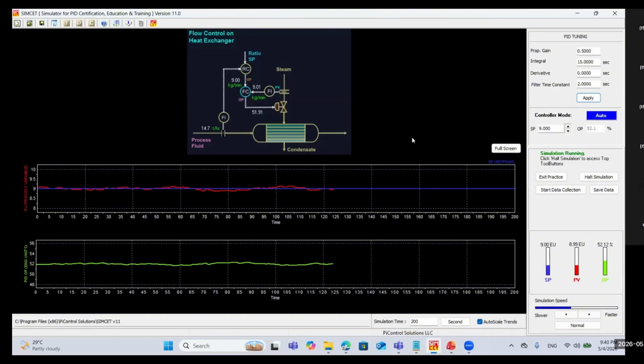Well, there are a lot of mistakes, but one of the biggest mistakes for me is that whenever you are requested to tune, you just go immediately and tune the controller. You don't understand the process. You don't investigate whether it is a valve issue, or an instrumentation issue. So it is not always tuning. Tuning cannot solve mechanical issues.